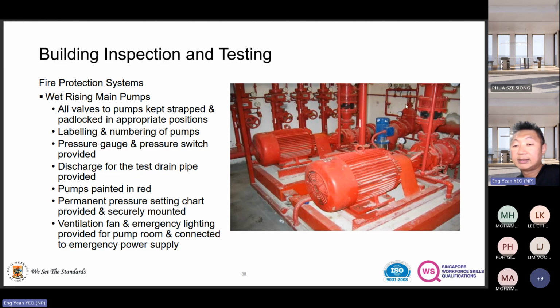Where is the incoming? Because usually for the older pump, you're unable to see the water flow. So, the pressure gauge switch is provided with the discharge drain valve. You need to see whether that drain valve is working or not, because that is where the fire protection guy is testing. The cut in, cut out of your pump: do they reach a certain pressure, then cut in? Do they cut in at the right PSI? Do they cut out at the right PSI? Pumps will be painted red for wet riser pumps. The wet riser pump is totally separate from the sprinkler pump because they are two different systems. Because it's high rise, you need to pump water higher. That's why the pumps are needed.